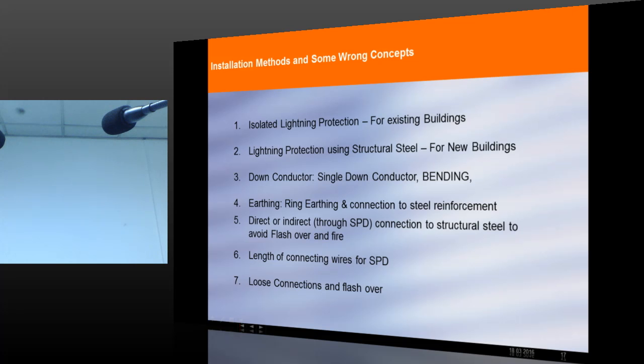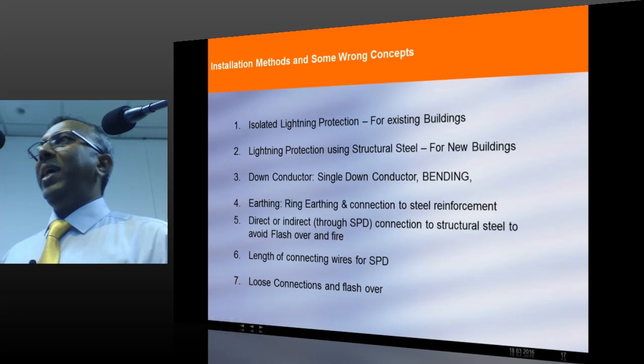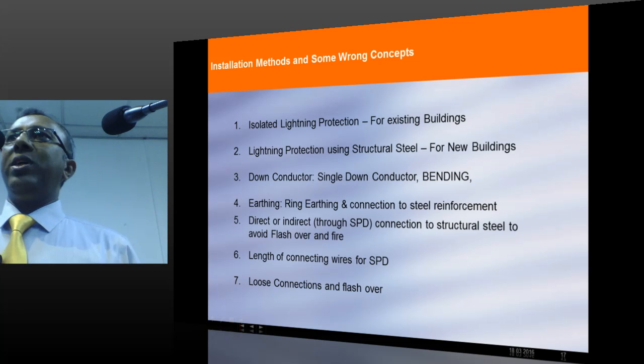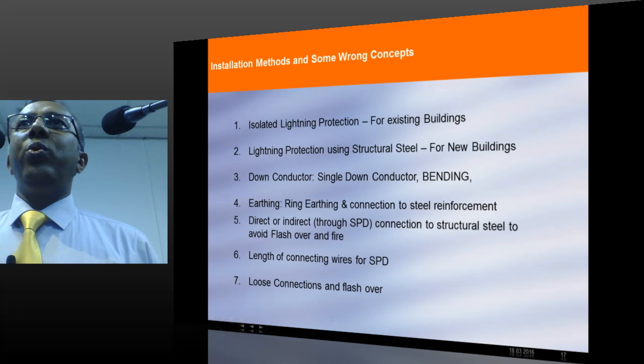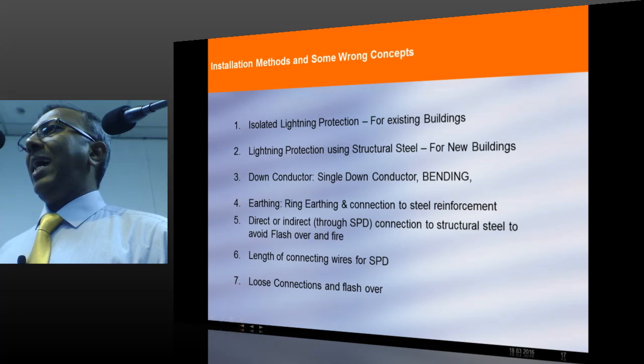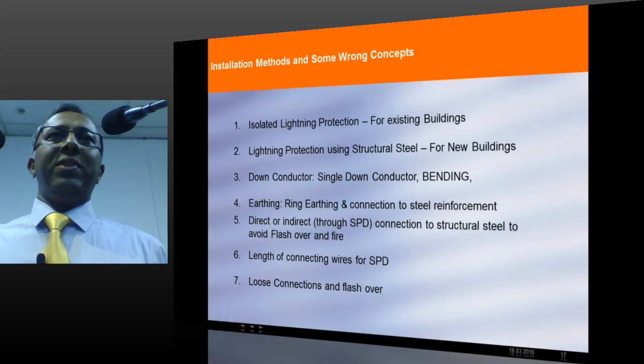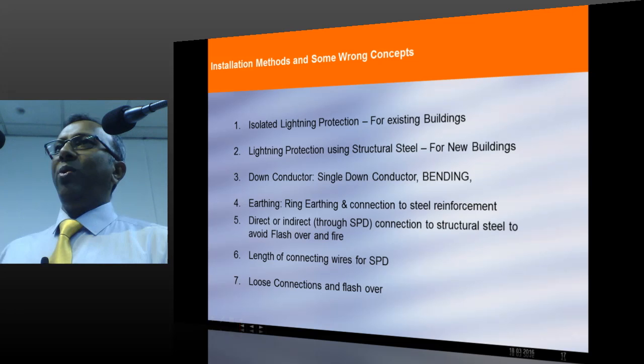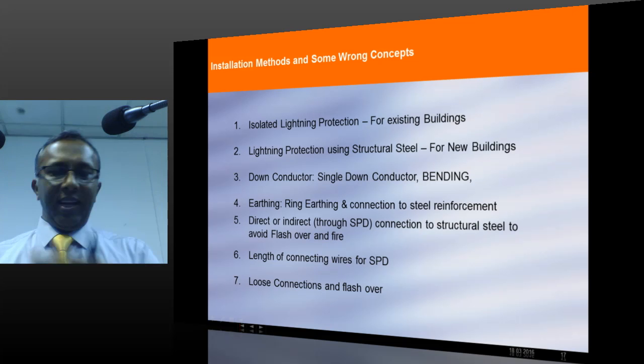We have additional information, and not we. The standard explains a lot of ways to convince your structural engineer why you have to have a connection between reinforcement and your down conductor, and under what conditions is also explained. Anyway, I will go into it in detail. But basically, if we explain to a customer that, look, you are going to construct a new building and you need to use your structural steel as part of lightning protection, generally 80% of the customers don't accept. Then we have to go with the standard and show it to them and explain in detail. But anyway, I am coming to that point.